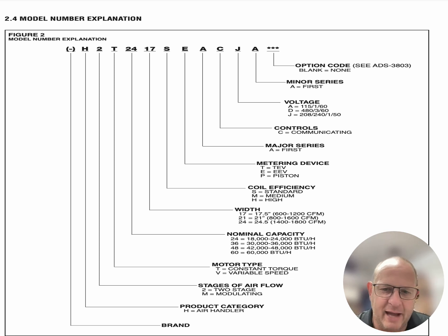Now, what I'm trying to look at here is this will tell me the voltage rating on the unit. It'll tell me the controls, how we're controlling this specific piece of equipment, the series of which it is, the metering device that's on it, the coil efficiency on the unit, the width of the unit itself, the nominal capacity, which is what I'm really, really concerned about on that particular unit. Motor types, types of airflow, stages of the unit, whether it's a two-stage unit or a modulating type of unit, and then the product category of this piece of equipment.